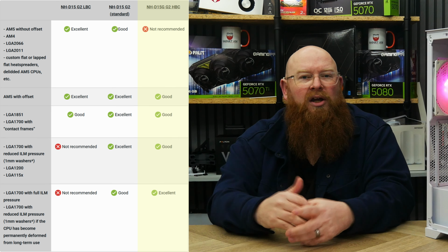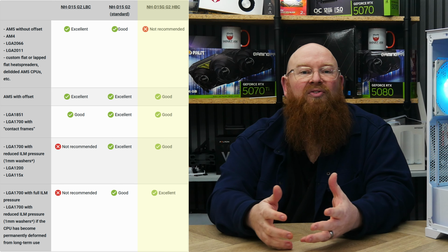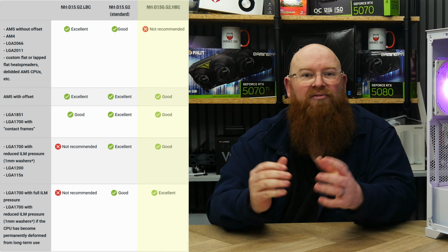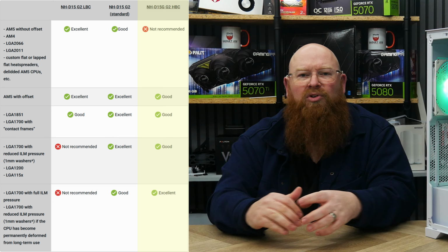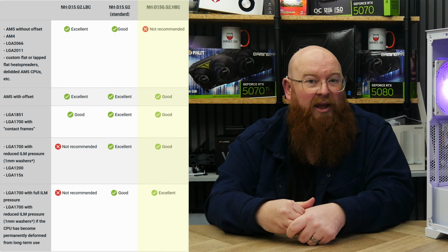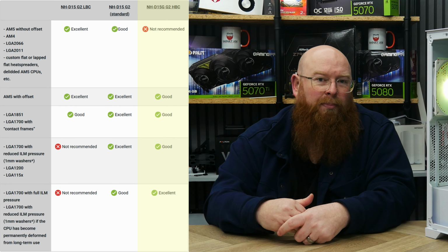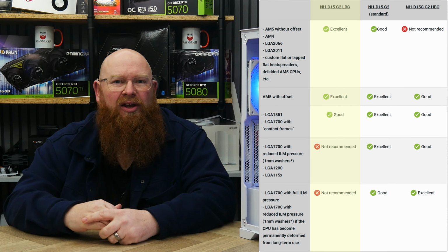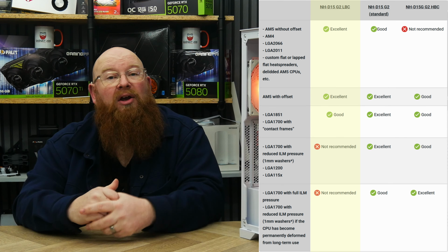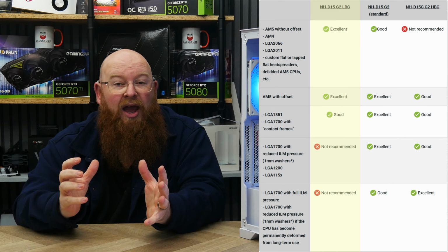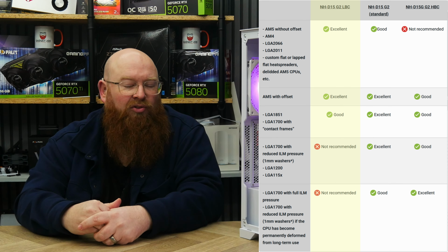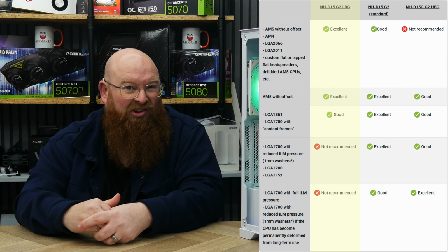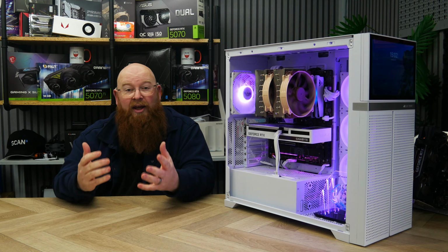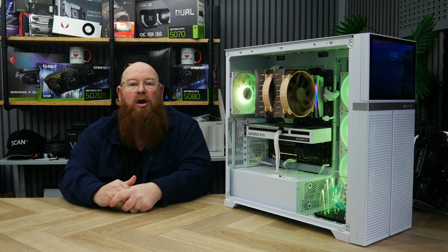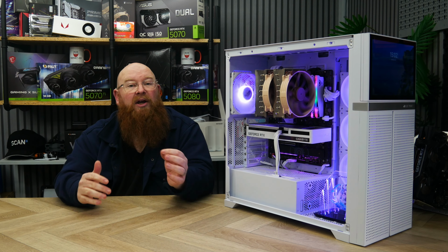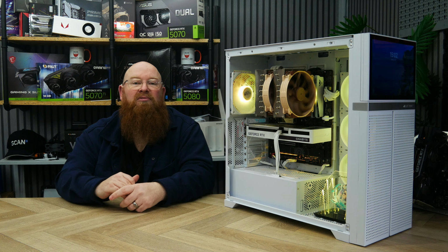Then there's the HBC, high base convexity, designed specifically for Intel LGA 1700 chips that have developed a concave warp over time due to mounting pressure. The deeper curve on this cold plate compensates for that deformation and ensures proper contact. And finally, the LBC, low base convexity. It's optimised for flatter heat spreaders like those on AMD's AM4 and AM5, maximising contact surface area on flat internal heat spreader designs. This level of engineering to cater for IHS variants across platforms is something no other manufacturer has done at this level. Pick your variant carefully, it does actually make a real difference.